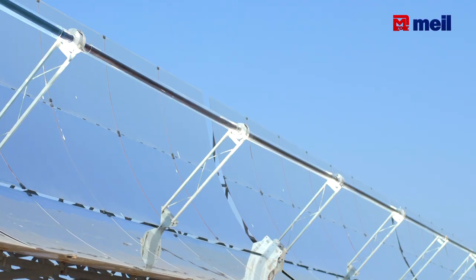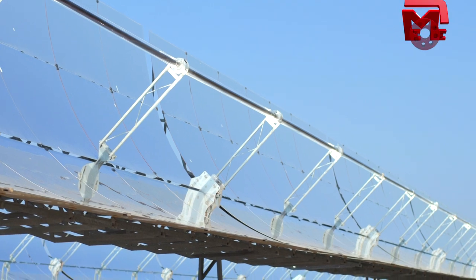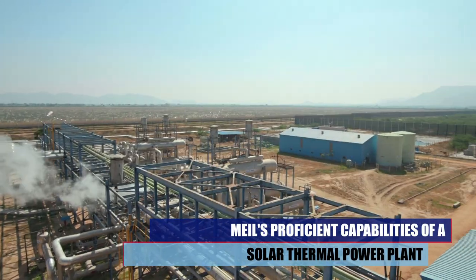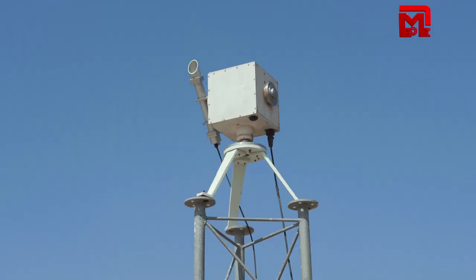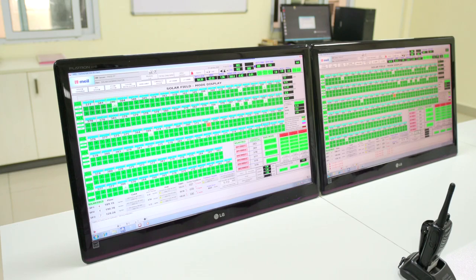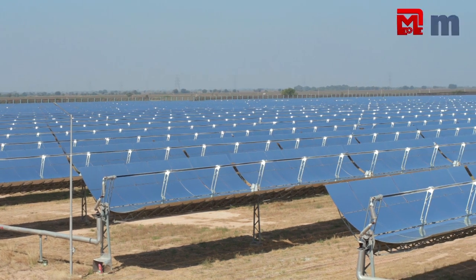After the incident radiation is collected in a parabolic trough, the radiation is converted into heating up of oil. The oil is further used in a heat exchanger where steam is generated, and the steam is used in a turbine to generate power. Being a solar thermal power plant dependent on the DNI, sun tracking is very critical. We maintain sun tracking accuracy of around 0.1 degree to ensure maximum energy is captured for the given mirror surface area.